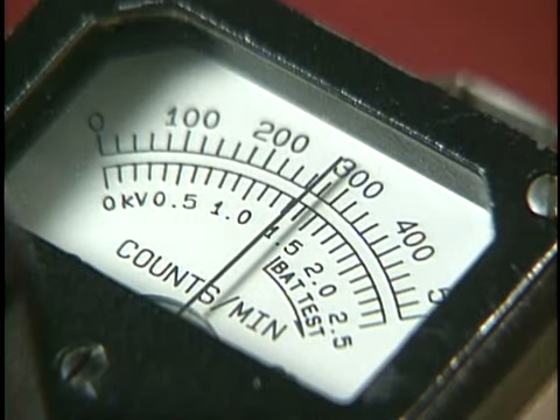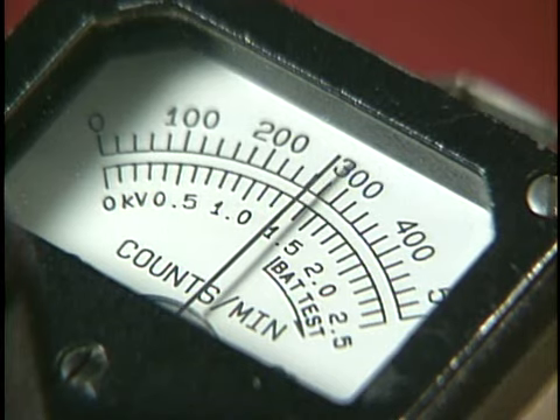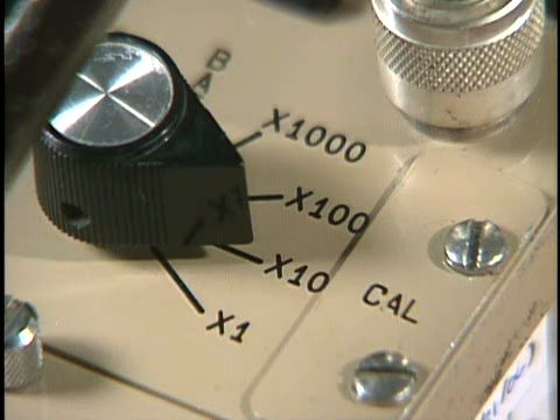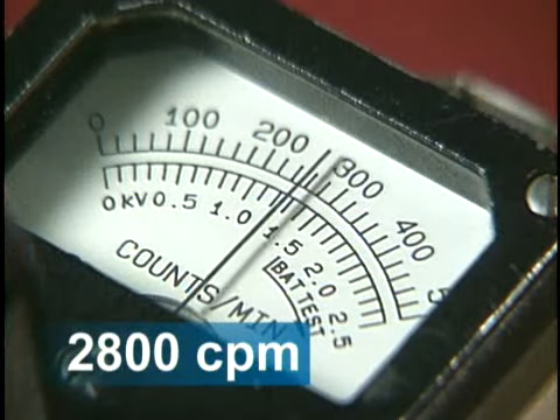Let's take a look at another reading. In this image, the needle is at approximately 280. You may think that the reading is 280 counts per minute, but remember to check the scale. Since the instrument is set at times 10, the reading is 280 times 10, or 2,800 counts per minute.